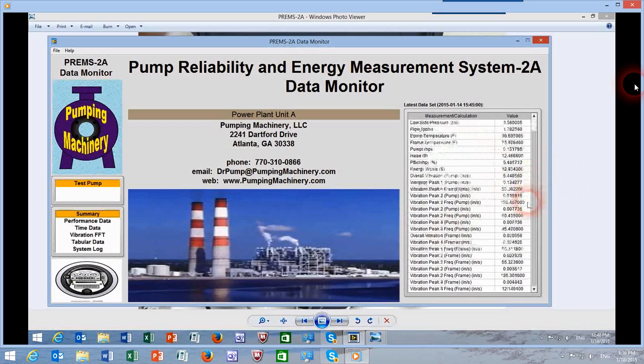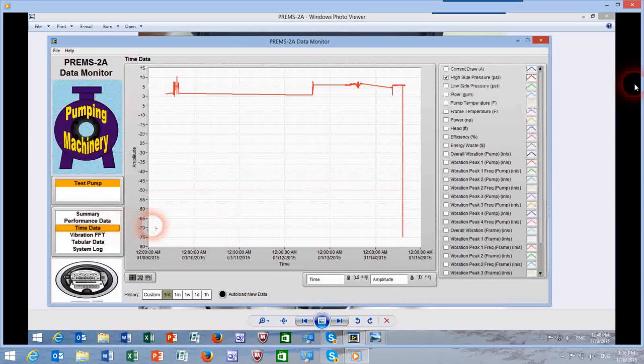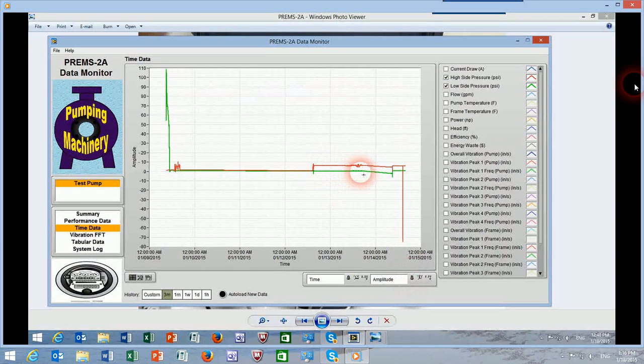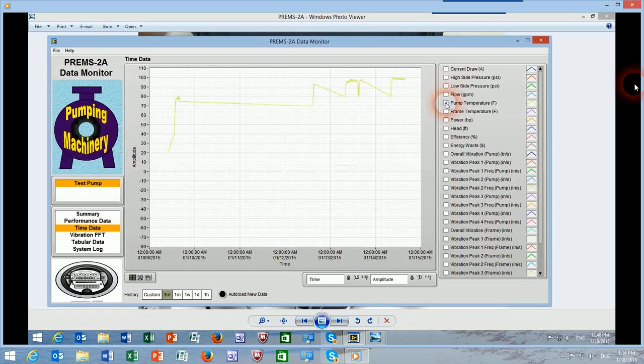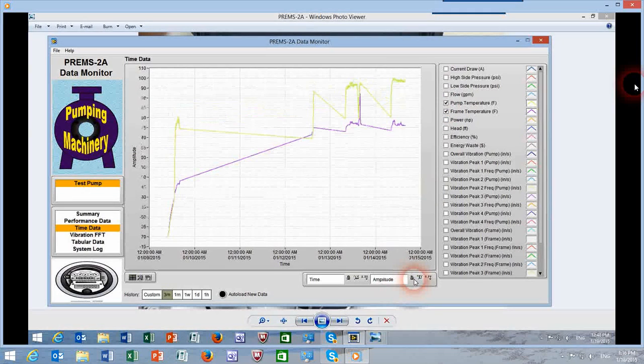That's a summary screen. If we look at the time data, the time data screen shows the variables. Let's pick high side pressure and low side pressure and display them on the screen. Well, we see that the pressure went from very high to very, very low and then became highly negative, which indicates perhaps the probe was disconnected, artificially showing the error. So we see that too. If we look at the frame temperature, let's try pump temperature and frame temperature. We'll see the trend. The pump started, the temperature increased, and then several times the temperature dropped down, indicating perhaps the pump was not running for some time.